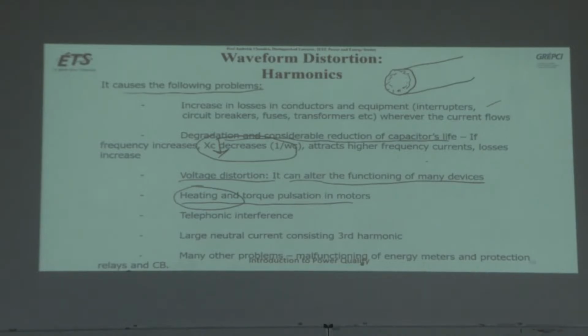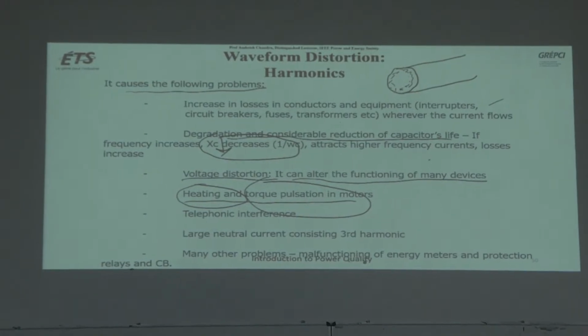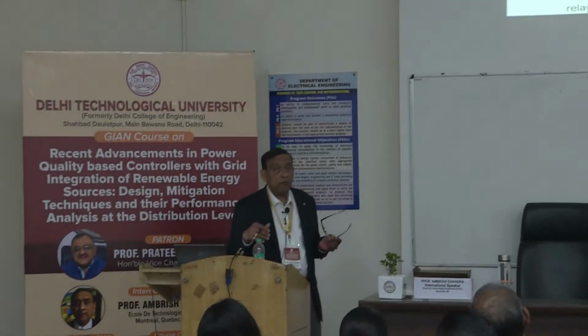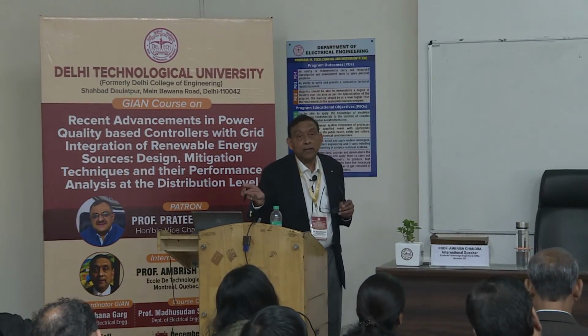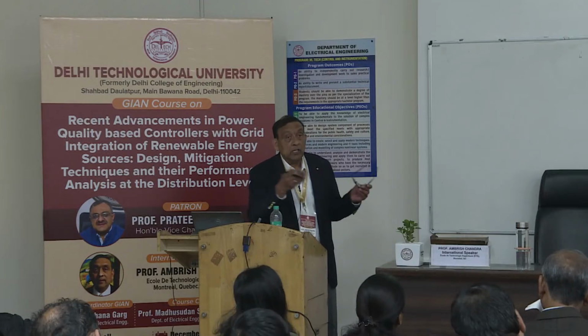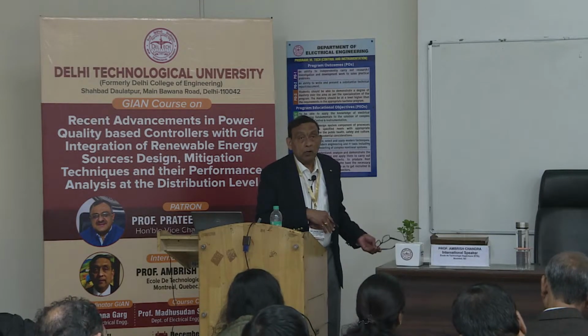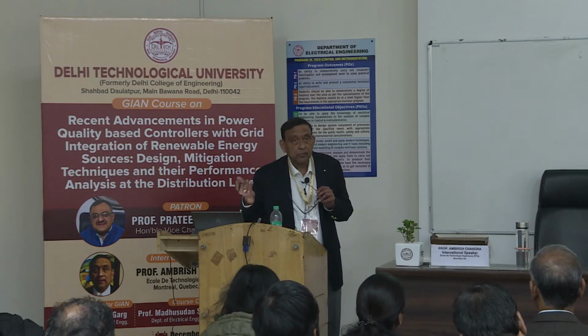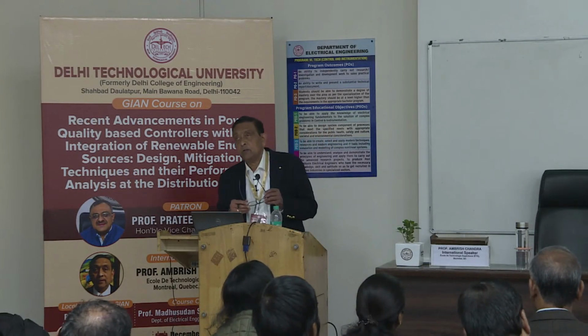See, different torques are created at the surface of the rotor because of the fundamental frequency, because of the fifth harmonic, because of the seventh harmonic, maybe there are 11th or 13th harmonics. That depends on what kind of voltage was there, right? So this will cause heating and torque pulsation. And why heating? Because you have a fifth harmonic, you have a seventh harmonic. So in the core of the machine, there will be ferromagnetic losses, hysteresis losses, eddy current losses. Hysteresis losses will be 5 times, and eddy current losses will be 25 times. So this will all cause the heating of the core of the machine.